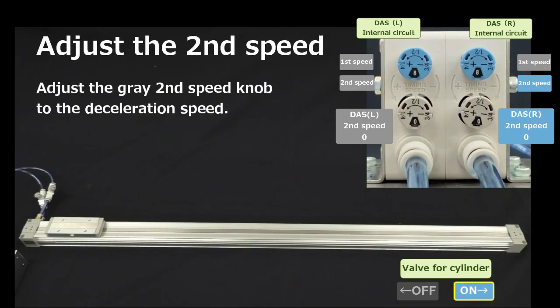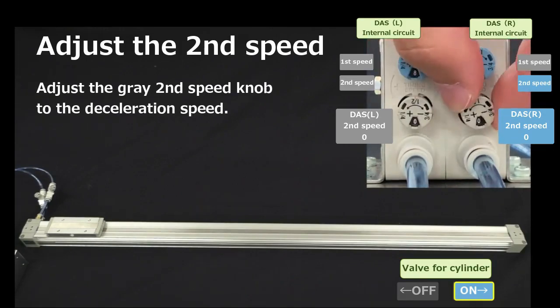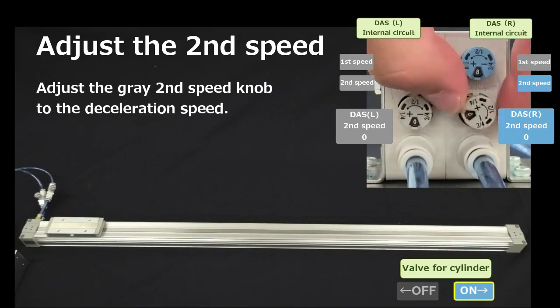Now, you can adjust the second speed. Gradually open the grey second speed knob until the desired speed is reached, and allow the cylinder to reach the stroke end.